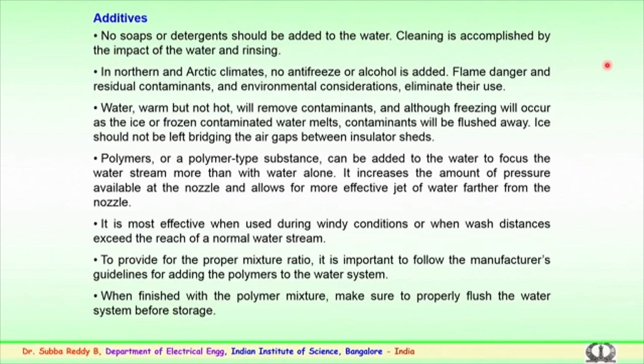Generally, cleaning is accomplished by the impact of water and by rinsing. In countries with northern and Arctic climates, no antifreeze or alcohol is to be added, because the flame danger, residual contaminants, and environmental considerations eliminate their use. So, no antifreeze or alcohol is added. Alcohol, soaps, or detergents should not be employed for cleaning, as they may cause a flame danger, or the residual contaminants could cause discharge activity or arcing.